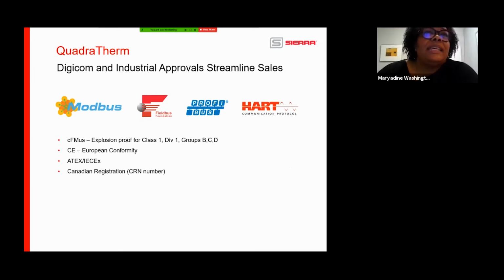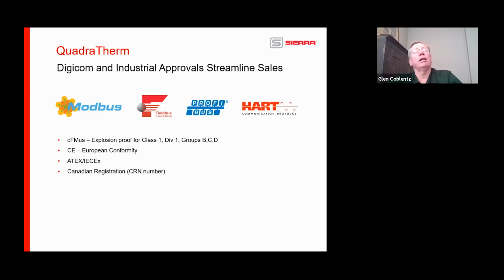He's asking, why are we calling it flare management system if it can be used for natural gas and all kinds of gas mix measurement? That's a good question. Typically, we call it flare management system because we're targeting main refinery flares, main chemical plant flares that already have $200,000 multipath ultrasonics in there.